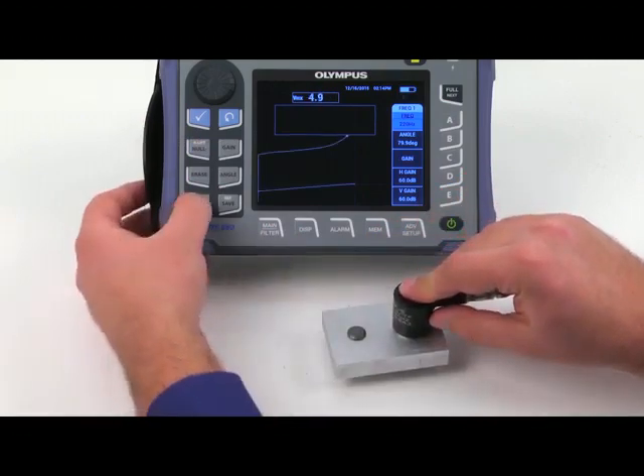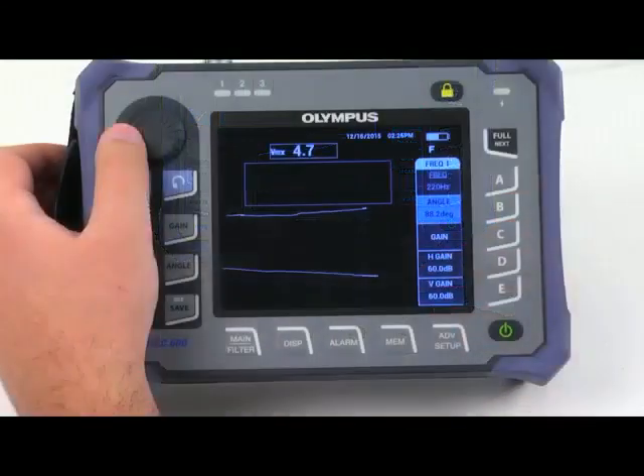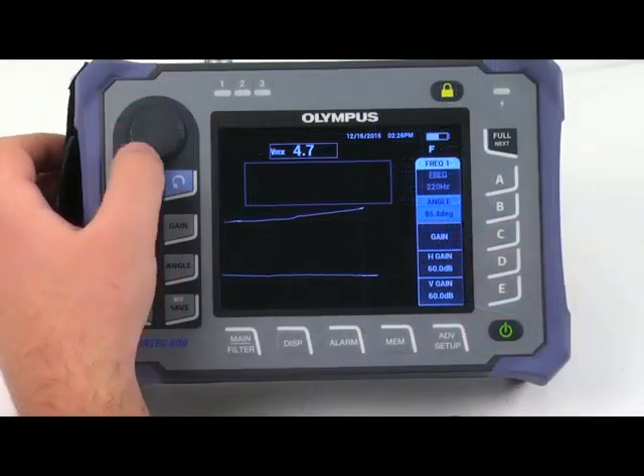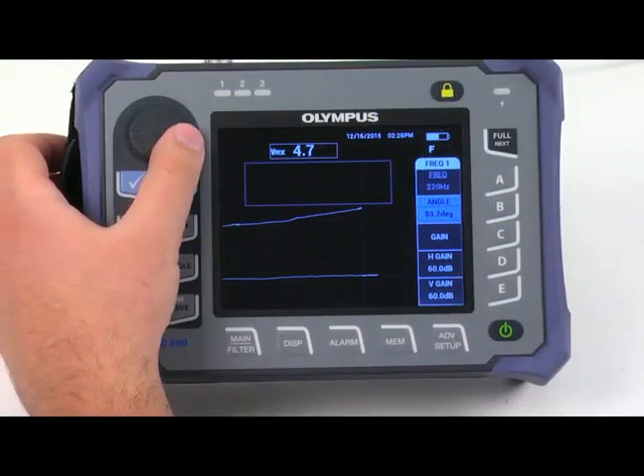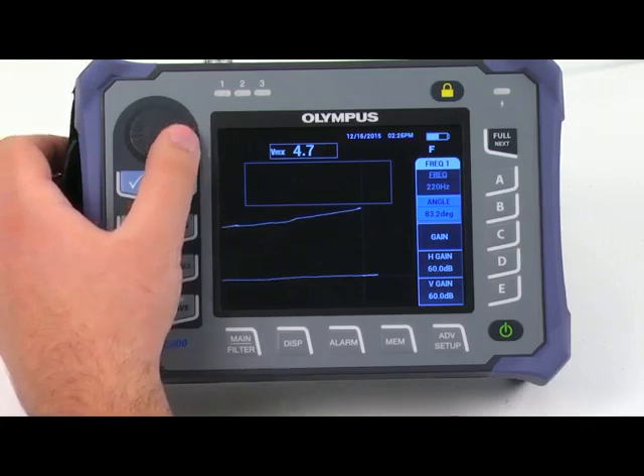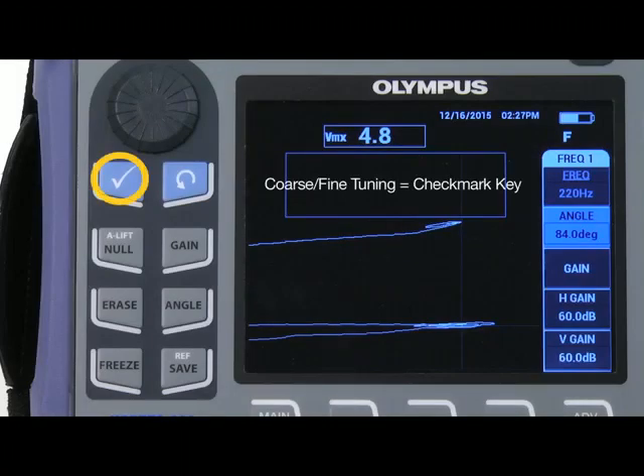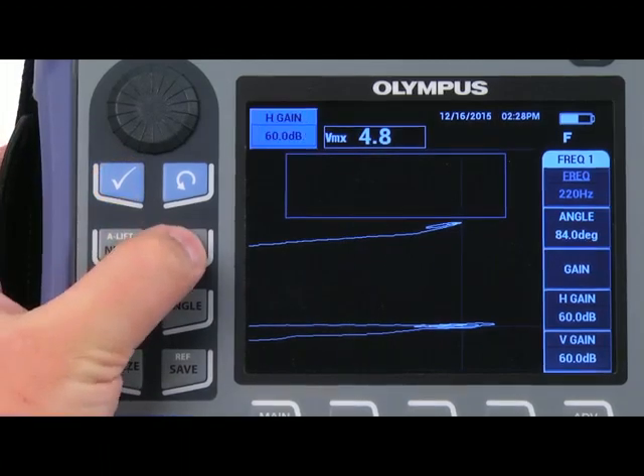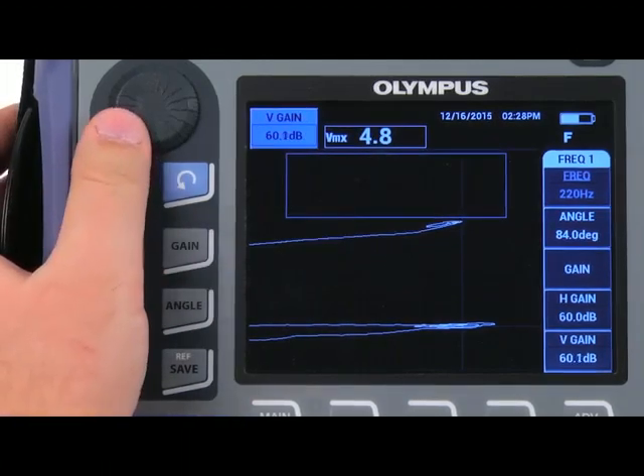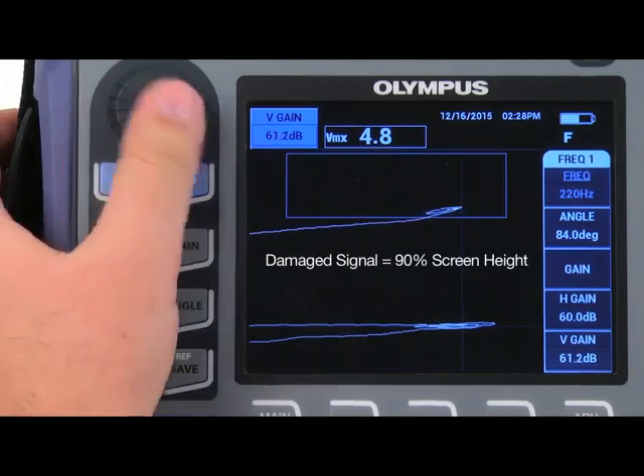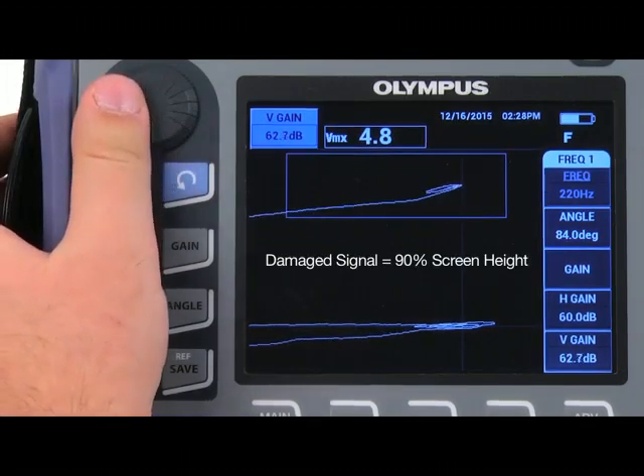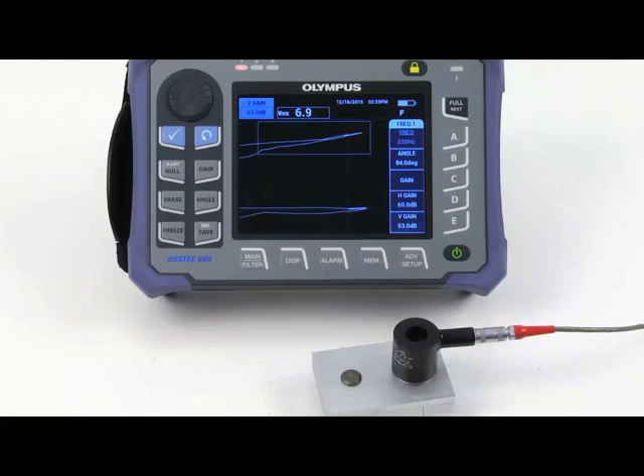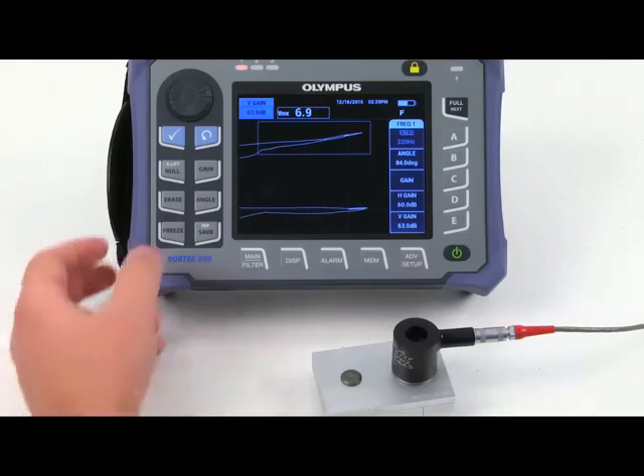Once the screen is frozen, you can change the angle. Try to set the liftoff as horizontally as possible. Use the knob to fine-tune the angle. To change from coarse to fine-tuning, press the checkmark key. Press gain 3 times to change the V gain. Set the gain so that the damaged signal reaches 90% of the screen height. Press freeze and full next to enter full screen mode.